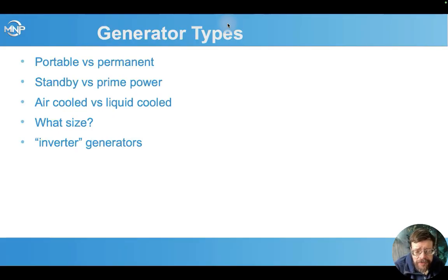One mention is inverter generators. These actually have nothing to do with inverters in PV systems. They're just a different design internally, which actually does have a small inverter in the generator. They can have better power quality for small generators versus the non-inverter type small generators. I don't know that I've actually seen an inverter type generator larger than about 7 kilowatts maximum, maybe. So while inverter generators are perfectly compatible with our inverter in theory, just the sizes that they typically come in mean that you probably won't be using one of those on a system with our inverter.